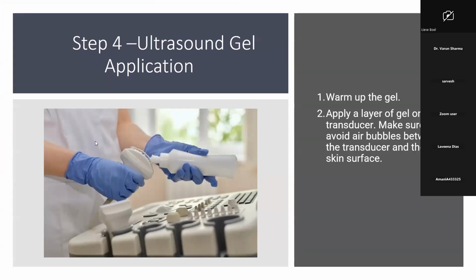The next step is applying gel. Very important step. When you use gel, it should cover the whole of the probe. It should be uniformly applied. You don't want a massive amount of gel in the middle with no gel at the sides. Then you're going to have significant dropout. Just remember, when you use the surface and you press hard, the gel basically gets pushed out. It gets thinnest at the bottom, and the gel at the sides does not go into contact. And that is what basically creates dropout in your images.